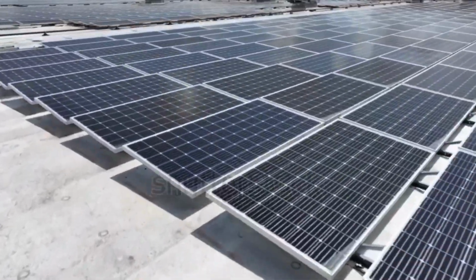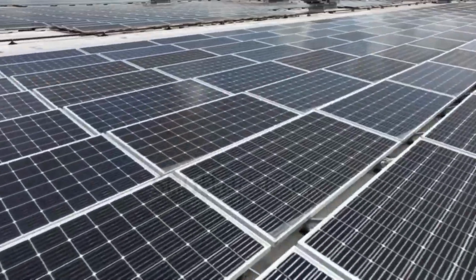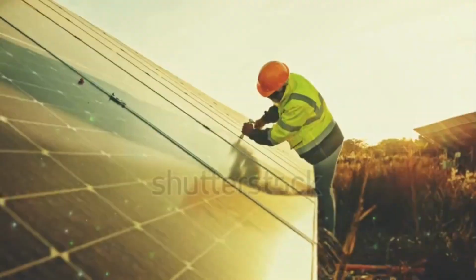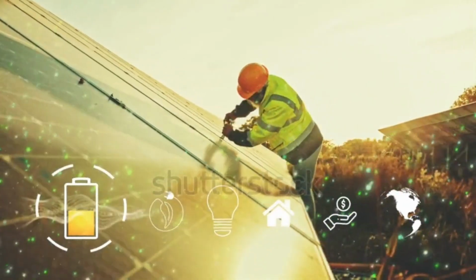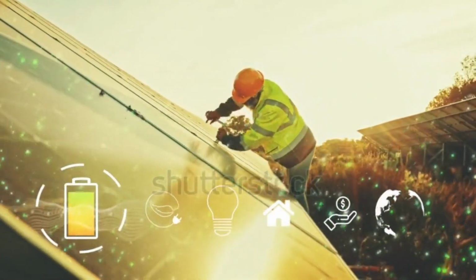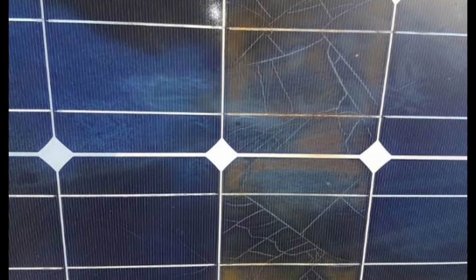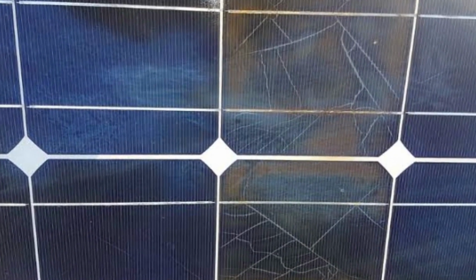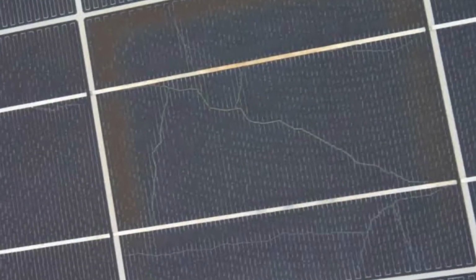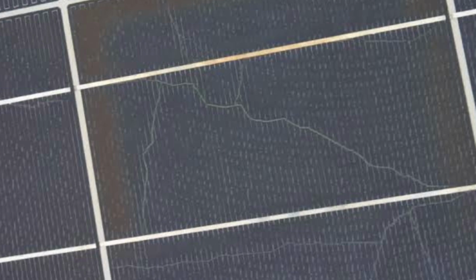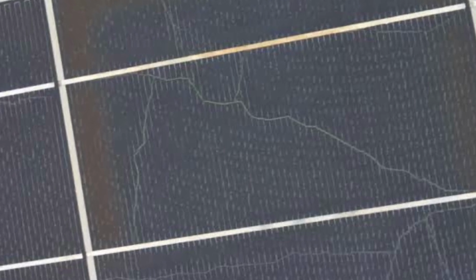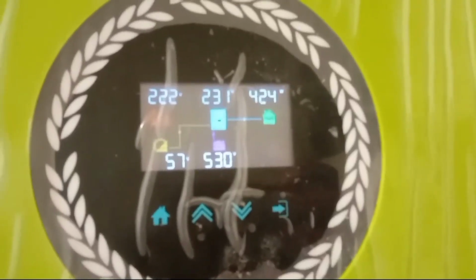Potential induced degradation (PID). This occurs when voltage differences between the solar cells and the frame of the module cause a loss in power output. PID is often a result of improper grounding or insulation issues. Microcracks in solar cells. Microcracks can form in the silicon cells due to thermal expansion, physical impact, or manufacturing defects. These tiny cracks can reduce the efficiency of the solar panel over time by disrupting the electrical pathways.